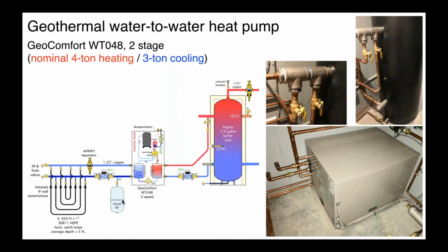We've actually written about this in Hydronics. If you take a look at, I believe it's Hydronics number 9 on geothermal heat pump systems. The fluids in an earth loop expand and contract, just like the fluids in any hydronic system as they change temperature. And one school of thought is that the piping also expands and contracts. So in a sense, you can say, well, as the fluid's getting warmer, the pipe's getting warmer, and it's going to expand. So therefore, you don't need an expansion tank. If the pipe is expanding and the fluid's expanding, you don't need a tank.